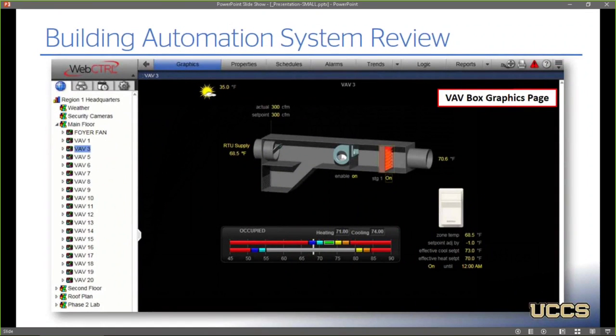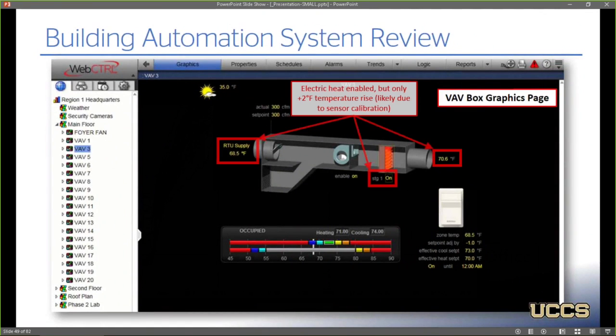And this is a screenshot of one of those VAVs. So you can see here the electric heat is on, but we're only seeing about a 2-degree temperature rise across the coil. And that temperature rise is likely due to sensor calibration. I'm assuming the heating coil is not actually doing anything here. And as I mentioned, that's typical of 6 VAVs.